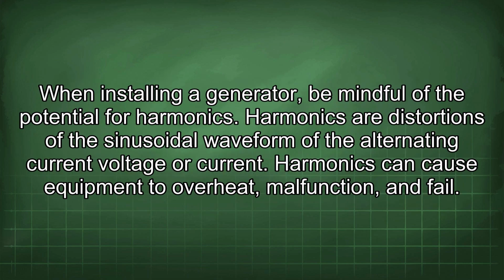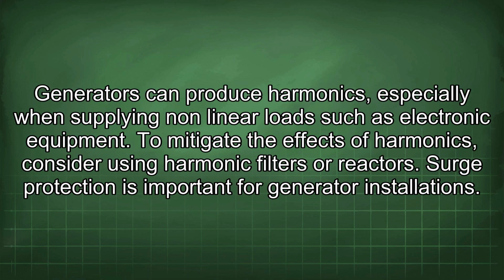When installing a generator, be mindful of the potential for harmonics. Harmonics are distortions of the sinusoidal waveform of the alternating current voltage or current. Harmonics can cause equipment to overheat, malfunction, and fail. Generators can produce harmonics, especially when supplying nonlinear loads such as electronic equipment. To mitigate the effects of harmonics, consider using harmonic filters or reactors.